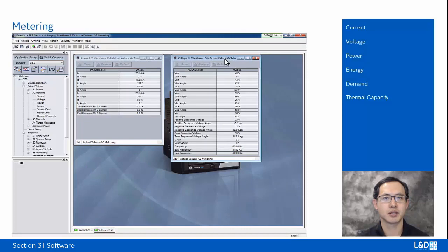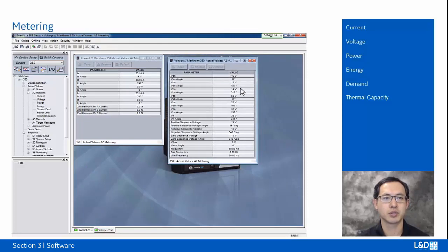And if we open the voltage, we can see the voltage meters with the phase to neutral and phase to phase voltage for the Y connection. If the VT is configured to delta connection, then only the phase to phase voltage will be displayed. There's also the positive and the negative sequence voltage, and this will be useful when we are doing the positive sequence under voltage testing. We can use these metered values to verify the pickup levels, and also the auxiliary voltage frequency metering in this voltage screen.